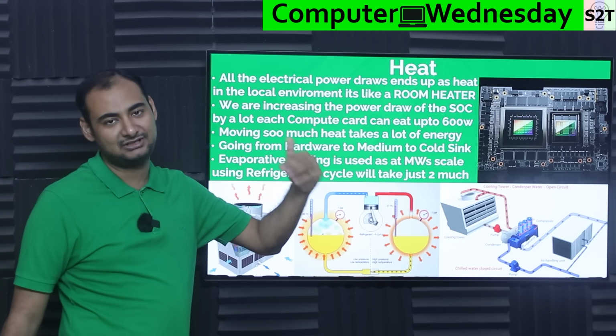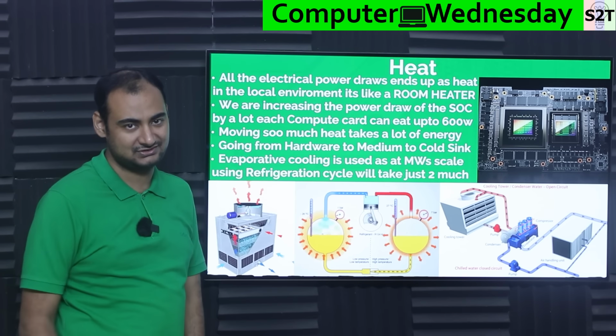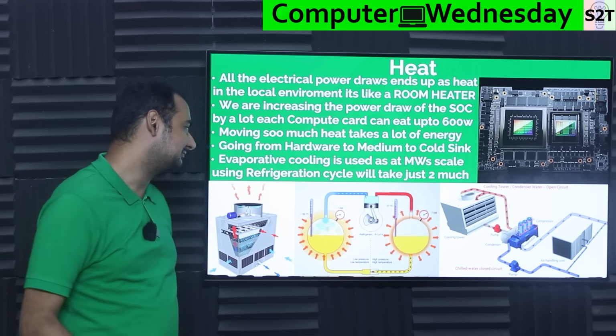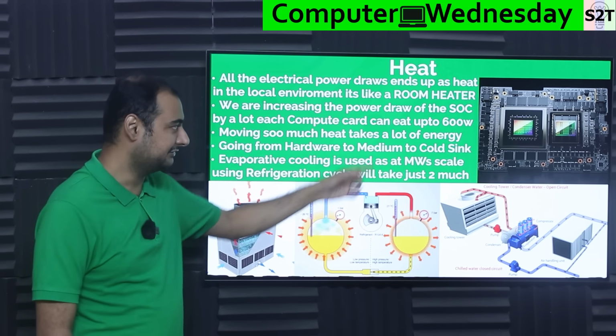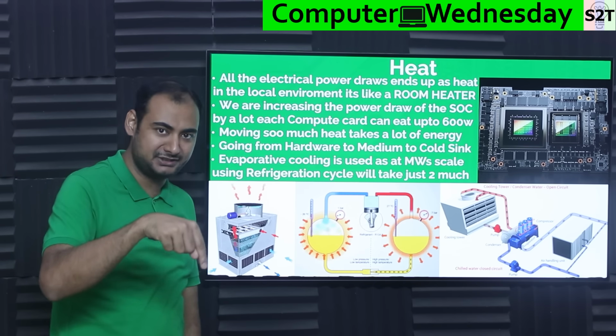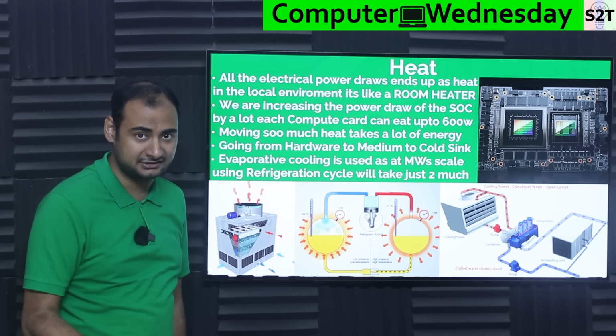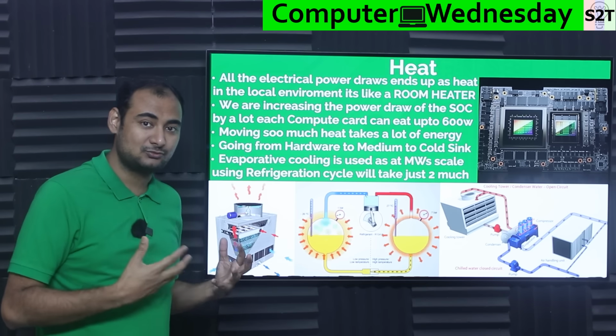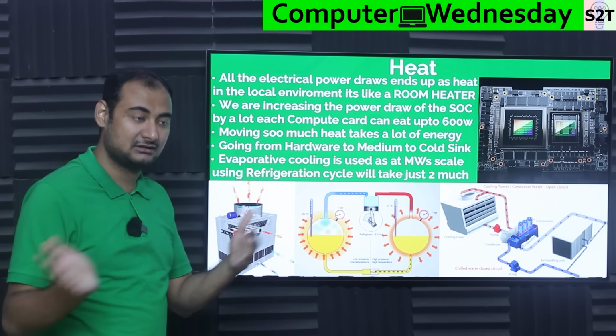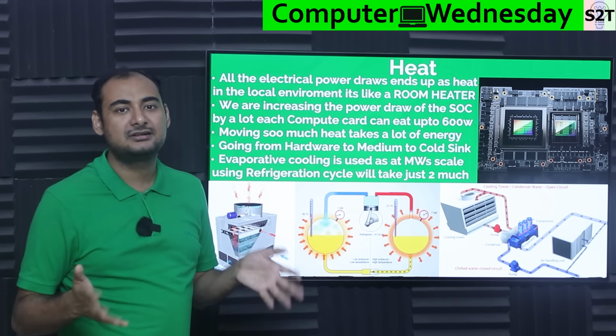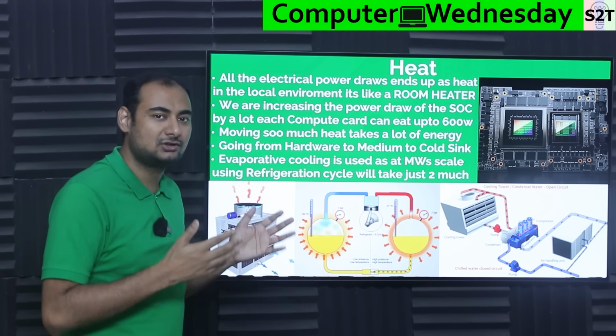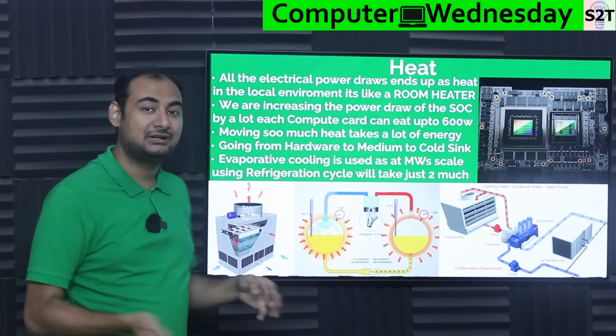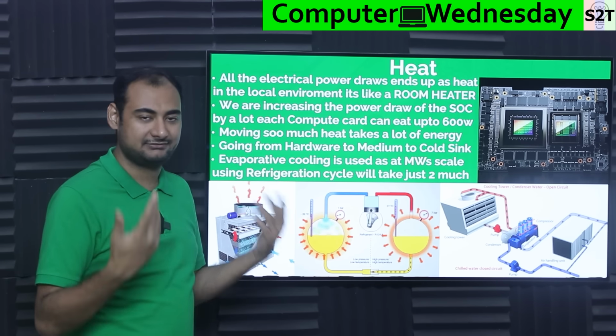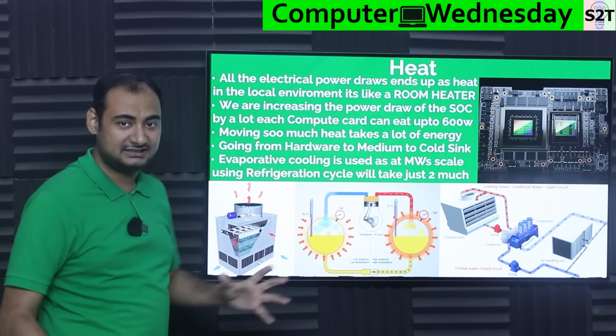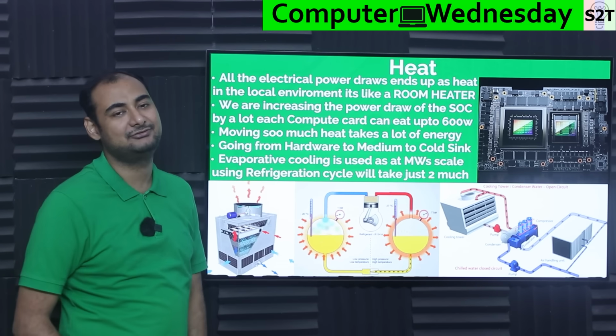Now, modern systems will not fry themselves - they will just downclock to uselessness. So you have to take heat from the hardware generating it and dump it into a medium, which in many scenarios is water. Because of so much heat and so much surface area required to couple that heat, it's hundreds of horsepower consumed just on the goddamn pumps. Then you have to send it all to the cold sink, wherever that may be. So you can understand the movement of heat itself is brutal.